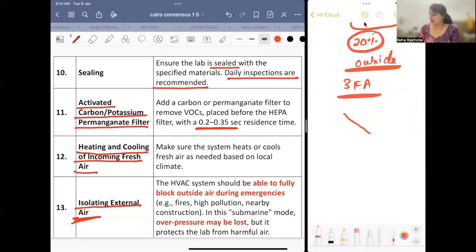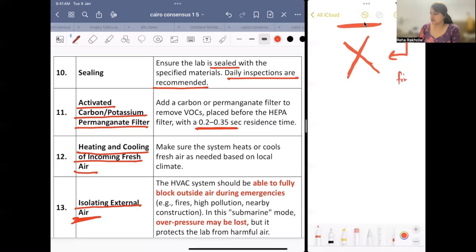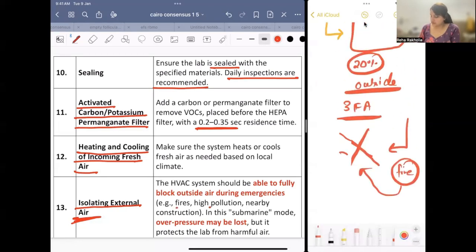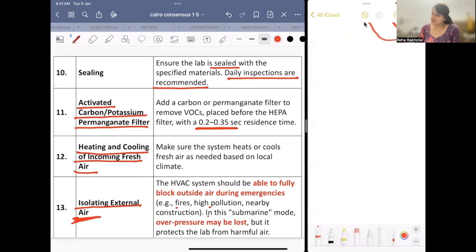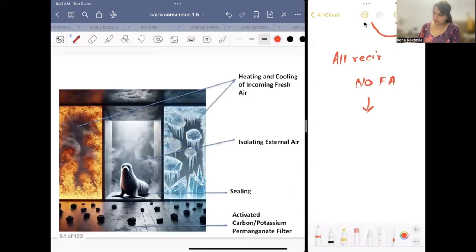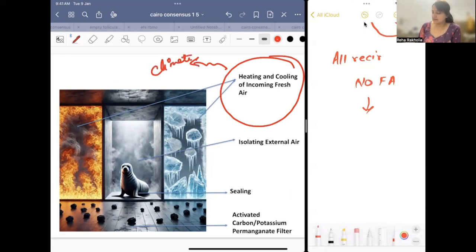So 20% was coming through outside air. But during an emergency, the ART lab should block the outside air, like when there is fire outside. We don't want any smoke to go into the ART lab, so it will block. No air from the outside will come in. This is the submarine mode, for fire, high pollution, or nearby construction. But what is the disadvantage of all recirculated air and no fresh air? It cannot maintain the overpressure, but it will protect them from the harmful air. See another picture mnemonic, heating and cooling of incoming fresh air. However the climate is, it can make the air suitable for the embryos.